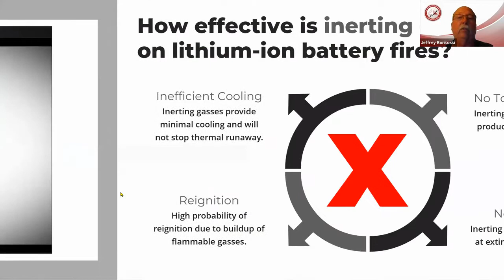The next one, probably very common - we see these in a lot of our data centers - are inerting gases. Inerting gases are efficient at smothering a fire by taking the oxygen out and creating a smothering effect, but they do little to nothing as far as cooling, and therefore they don't stop thermal runaway.